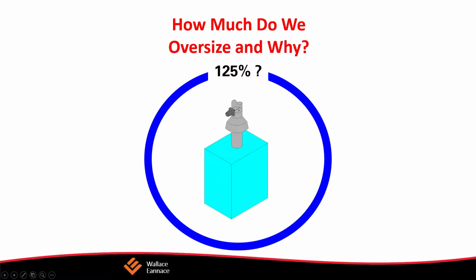It makes for simplicity of operation, and also the controls will often require that. Lochinvar does offer an interesting option, which I'll speak a little bit about. We do a thing called front-end loading. So in this particular case, what you see here is 2 plus boilers, which provide the majority of heat. But when you get to that 0-degree day, which happens very infrequently, there's no requirement to have a condensing boiler. We can put a non-condensing.